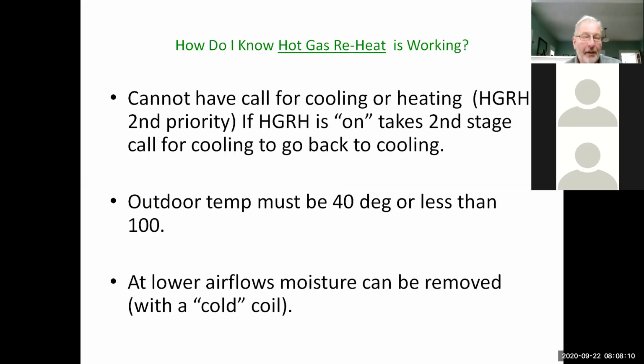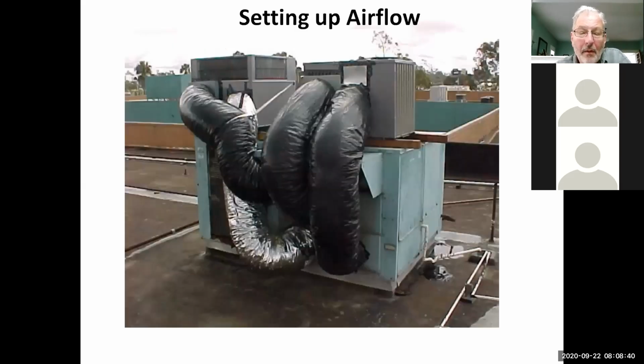Couple things to remember, it's a cooling priority. So if it's in a cooling call, it's not going to go into hot gas reheat. The cooling call is going to take priority, and if it's under 40 or over 100, it's not going to dehumidify. So if you need something to run in colder climates or colder conditions, this probably isn't the right unit for you. Best use on these is convenience stores. That's where we see a lot of these go in. So that's the dehumidification unit. This is called the low bid.